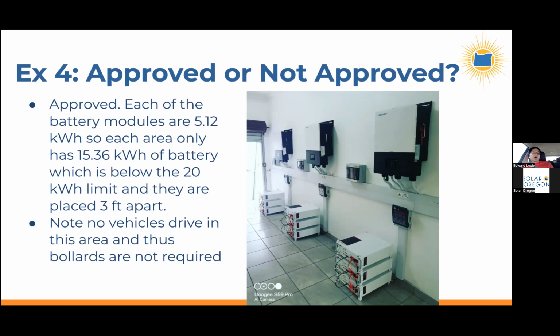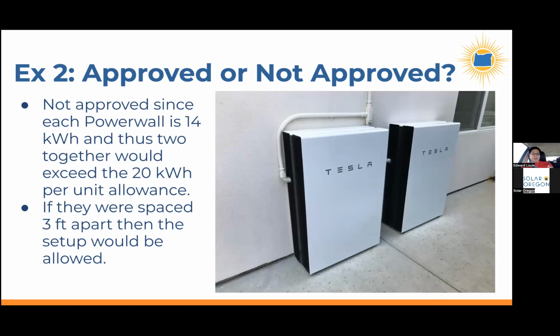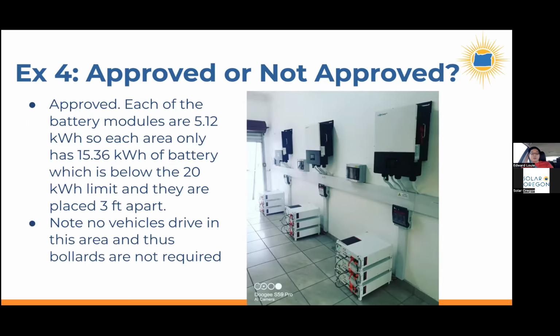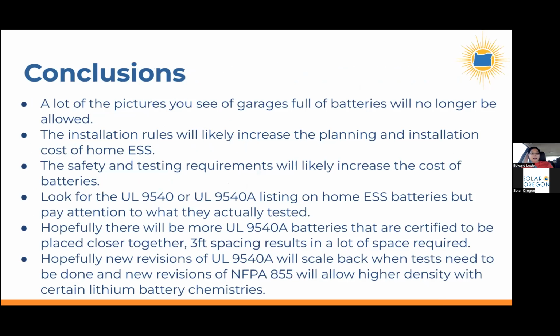So I actually had a hard time finding a picture of a battery installation that actually meets the NFPA 855 requirements, because there are so many battery pictures like these, and these are no longer approved under the new rules. So that's what I'm saying. These new rules are very impactful, and that brings us to one of the conclusion points, which is that a lot of the pictures you see of battery setups in the field are no longer really allowed under the new rules, or they can't be installed exactly the same way. You need to do some modifications, like space them further apart. These new rules will likely increase the planning and installation costs of home energy storage systems.